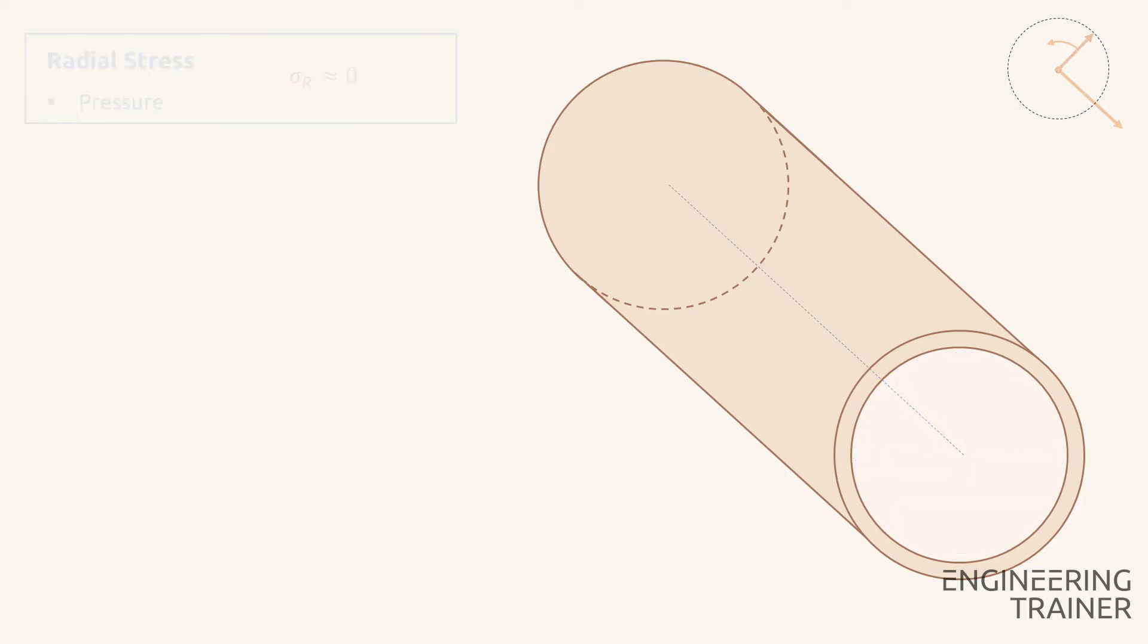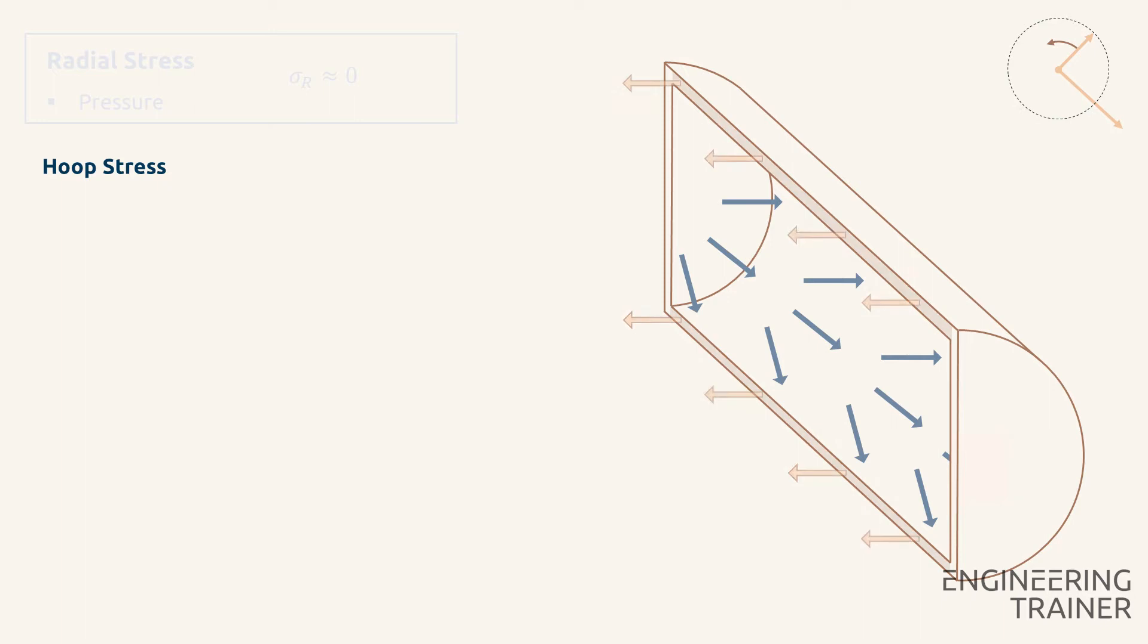Next, let's evaluate the hoop stress. The pressure causes a hoop stress that is calculated by PD over 2T. Also for the hoop stress, it is the pressure only that contributes. No other load causes an overall stress in the circumferential direction to a piece of piping.